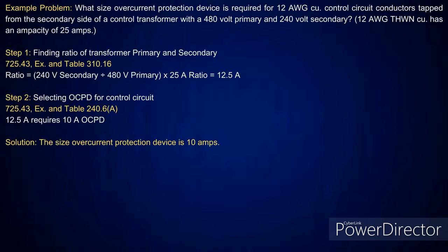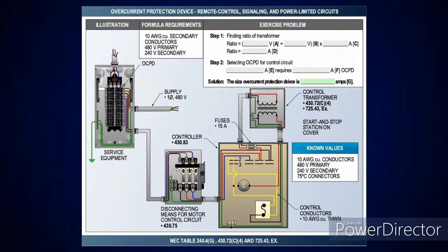Right. Okay. It's all very simple, but what is the main thing I did? I got my amperage first. That's all I'm trying to do. And in this case, there's no percentage or anything. All I'm trying to do is determine this based on the ratio of the transformer. Okay. And basically the ratio of the transformer, when you see that and you do the calculation, you're going to see it matches up to the conductors. That's basically what they're doing here. Okay. So we just try to prove everything basically, so you understand what you're looking at.